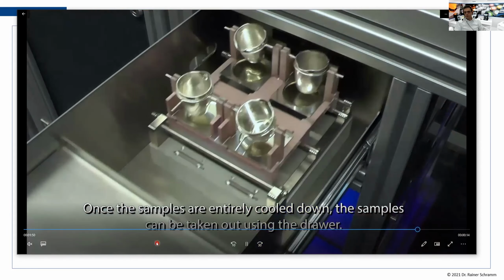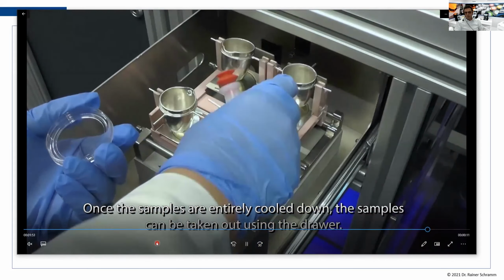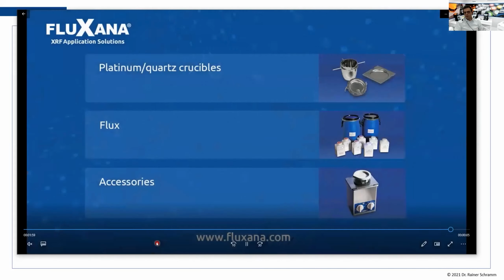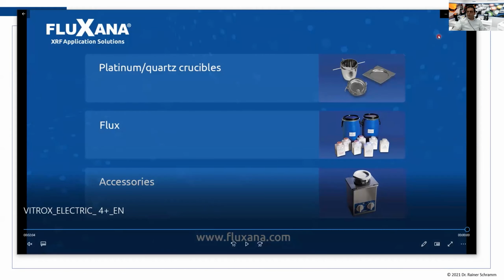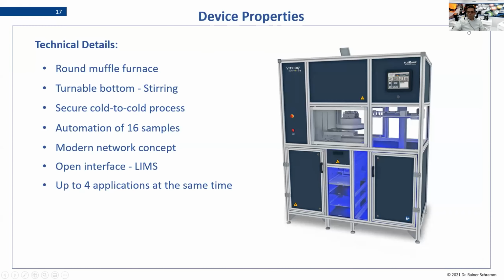And once it's cooled down, you just take back crucibles and molds. This is already after the cooling. In between it was sitting about 6 minutes in the cooling, and then you can ask the autosampler to give you back the samples. Also important is that you can interrupt the whole process. Once one sample is fusing, you could unload finished samples and load new samples. This is already going independently, so that you can run the machine in continuous operation. Samples are going in, samples are going out all the time. Or you just load it in the evening, full with 16 samples, and in the morning you have 4 different applications fused.